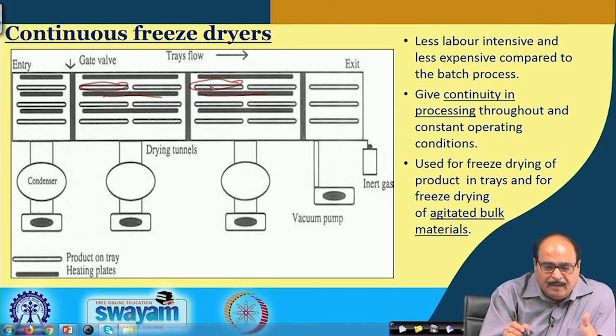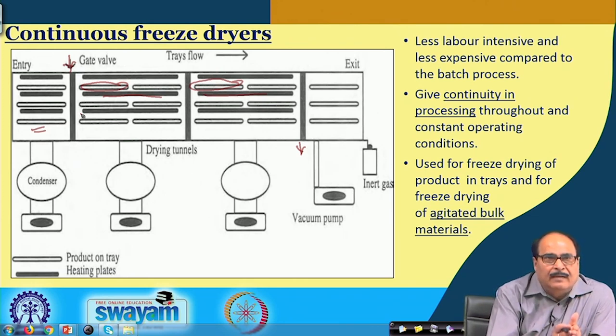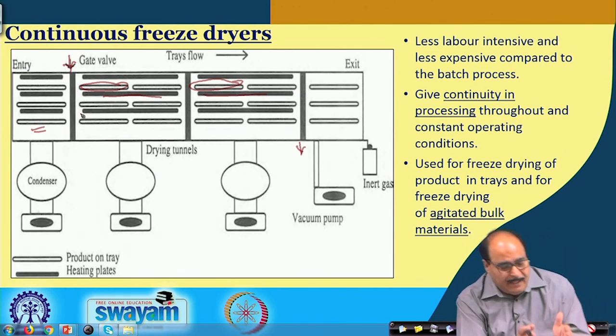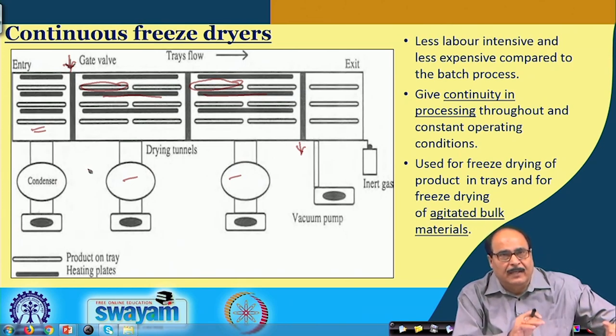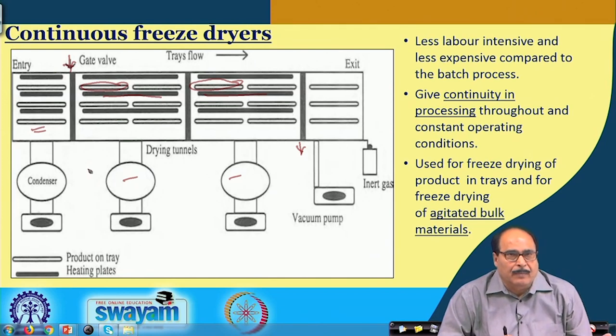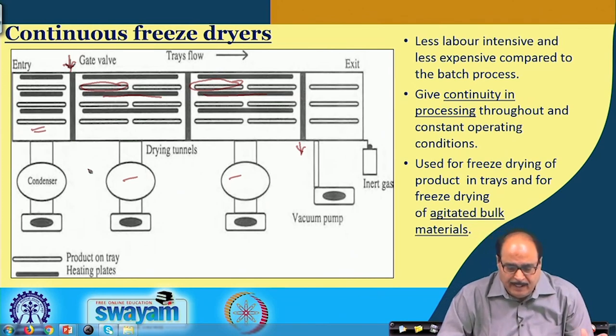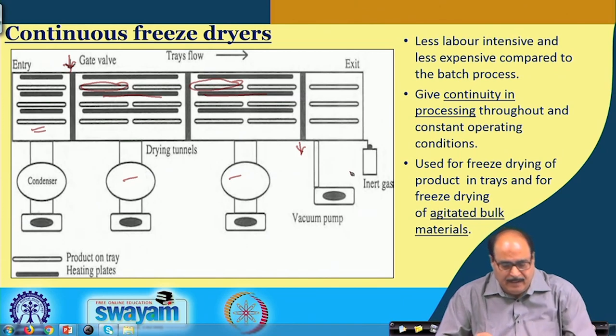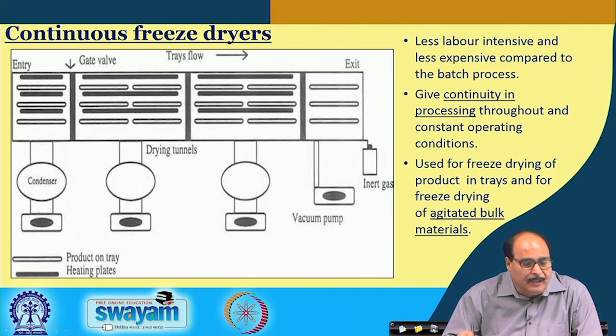There is an entry lock and an exit lock. The product is loaded in one section, then moved to the next section — the entry lock is opened or closed and the product moves from one section to another. Every section is provided with condenser systems. This is the drying tunnel. The material on a conveyor belt is kept in trays, the trays move and come in contact with the heating plates. Inert gas is used to open the exit lock and the material is collected at the end of the process.